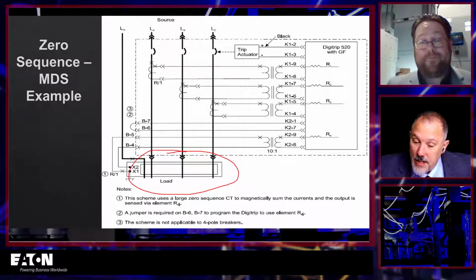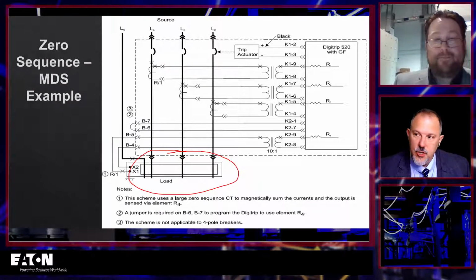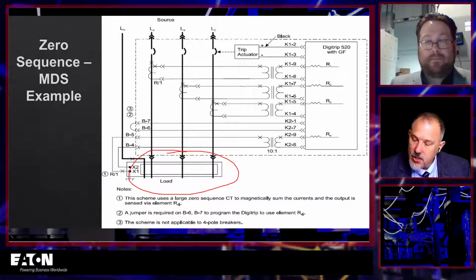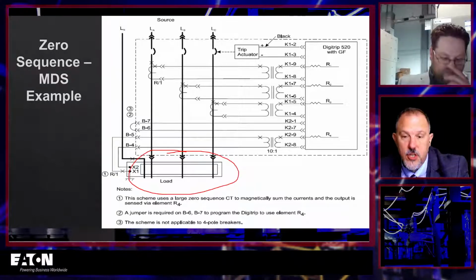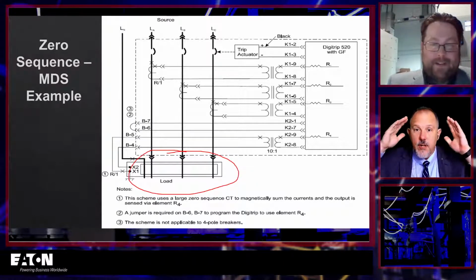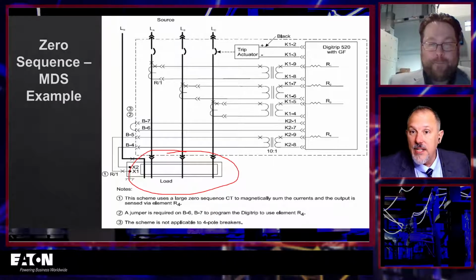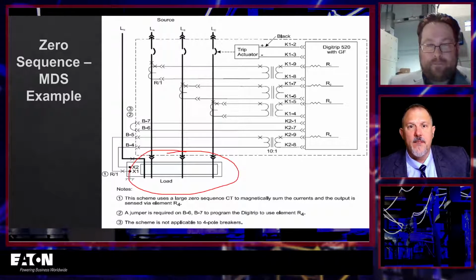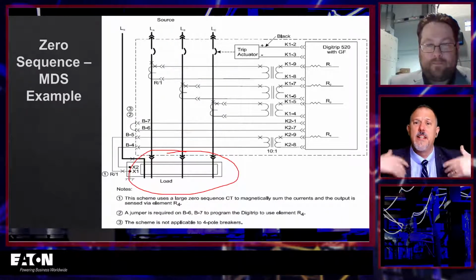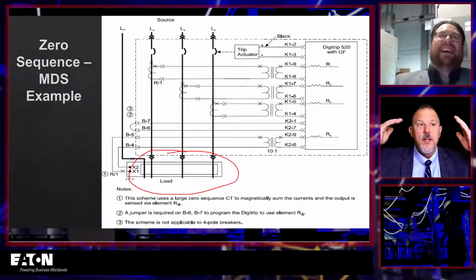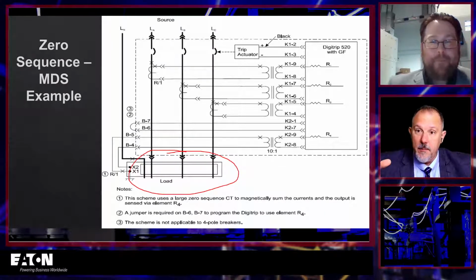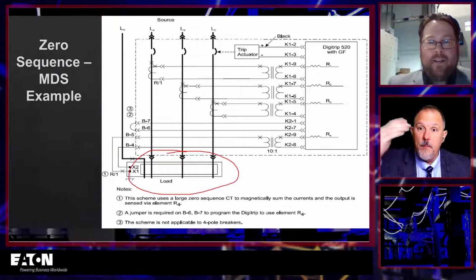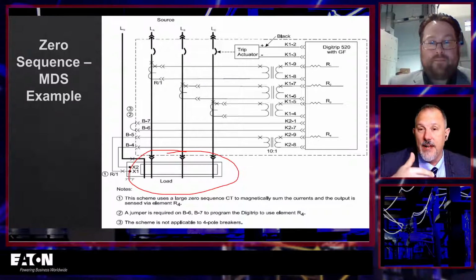And that's why it's really important from a person who's doing it. If you look at the latest version of the National Electrical Code, we said a qualified person because it's more than just a qualified person on this relay. If you're looking at a lineup of switchgear, whether it's my switchgear or one of my competitors' switchgears, which I don't think anybody would ever have to test because nobody installs that stuff, everybody installs Eaton equipment, right? But you have to know the equipment itself to know which buses are A, B, and C, how you're going to clamp on, what you need to turn off and isolate, all that good stuff.